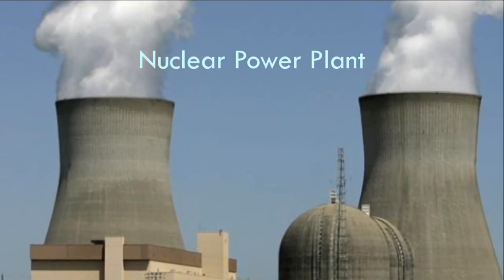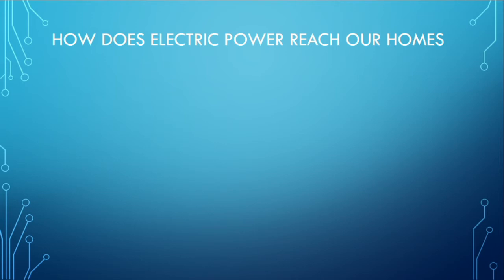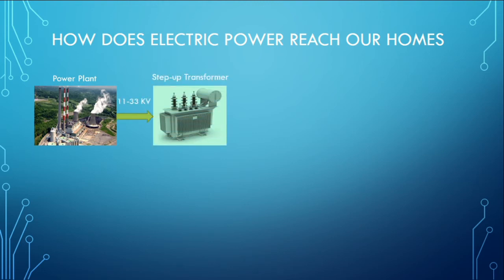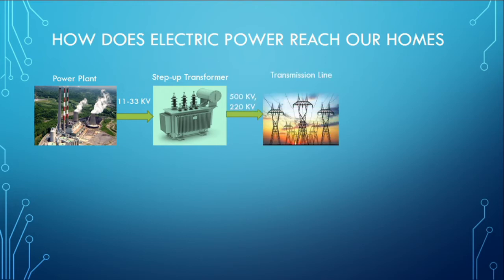Coming back to our main topic, the power plant generates electric power normally in the voltage range of 11 kV to 33 kV. This power is then fed to a step-up transformer, which steps up the input voltage to 500 kV or 220 kV depending upon the distance of the transmission line. This is not actually just a simple transformer, but a whole substation at the generation side.